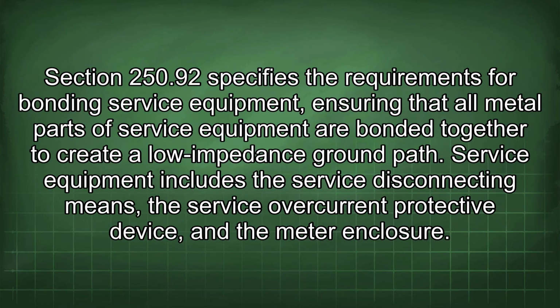Section 250.92 specifies the requirements for bonding service equipment, ensuring that all metal parts of service equipment are bonded together to create a low-impedance ground path. Service equipment includes the service disconnecting means, the service overcurrent protective device, and the meter enclosure.